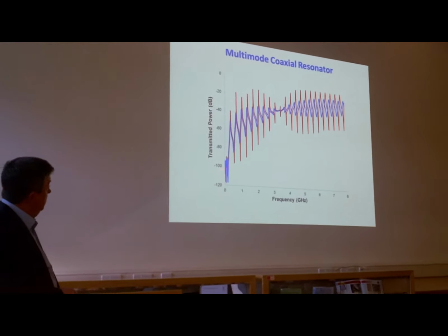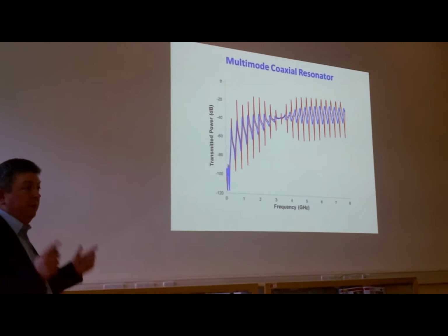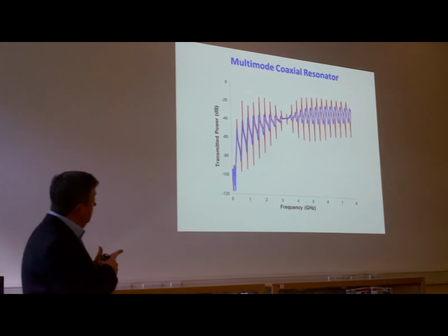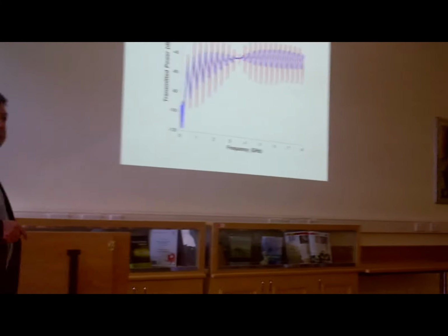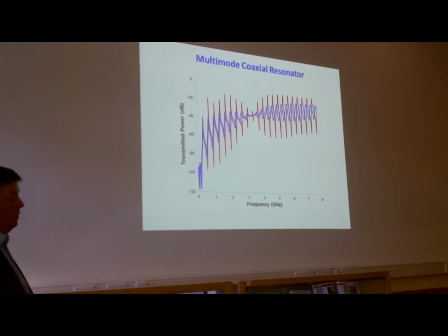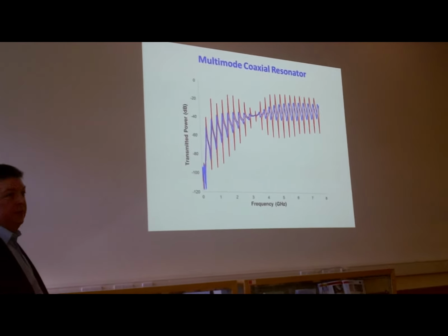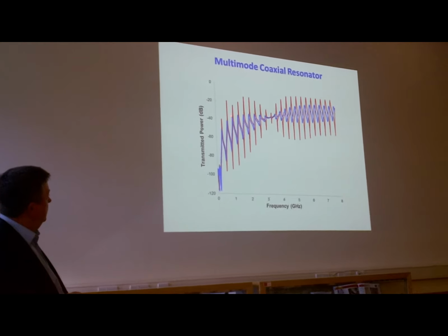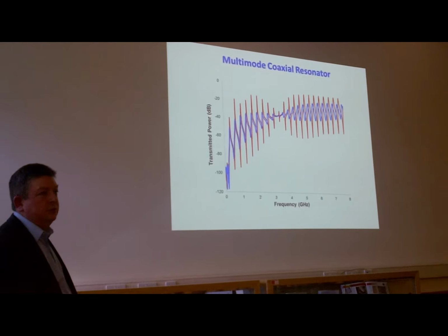This is another type of resonator. It's a very simple resonator based on a coaxial cable actually. So we can take a commercial coaxial cable like this, make it a certain length, chop its ends off so it's an open circuit resonator. So at the end we have a strong electric field, and then we can dip that into anything we want and then get some dielectric property measurement of the thing that it's dipped in. So this is an ideal sensor really, as a T-piece in a stainless steel tubing type system.